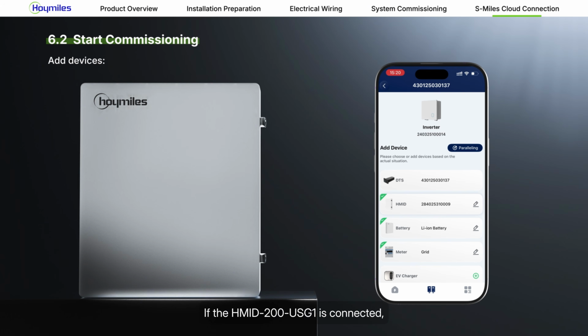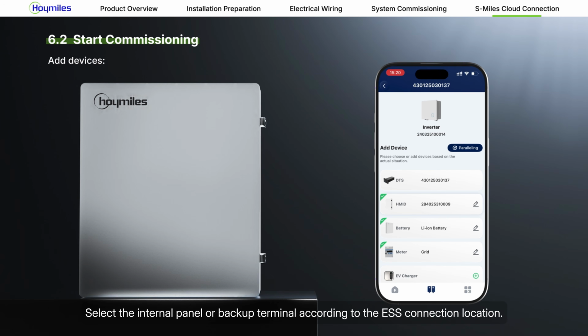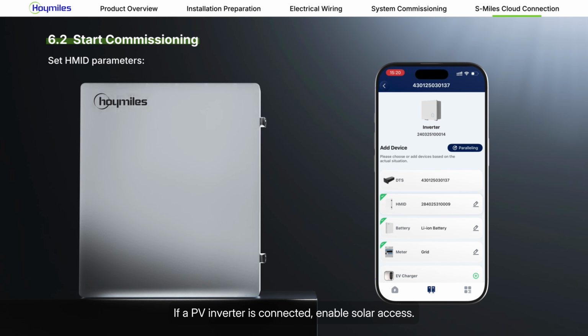If the HMID-200-USG1 is connected, the HMID will be automatically recognized. Click HMID to set relevant parameters and save them. Select the internal panel or backup terminal according to the ESS connection location. If a PV inverter is connected, enable solar access. If a generator is connected, enable generator access. Set the rated current of the incoming circuit breaker. The default value is 200A, with the range of 100A to 200A.